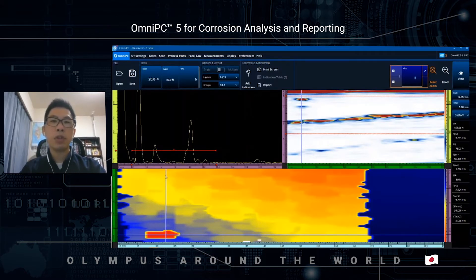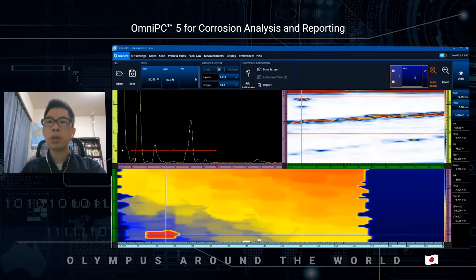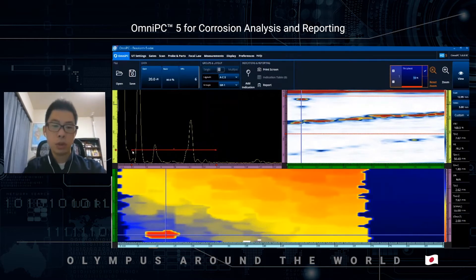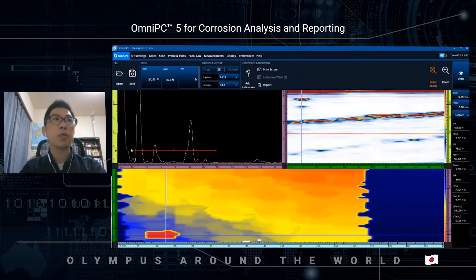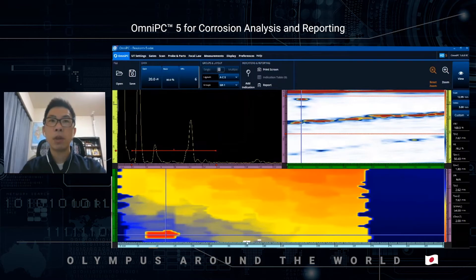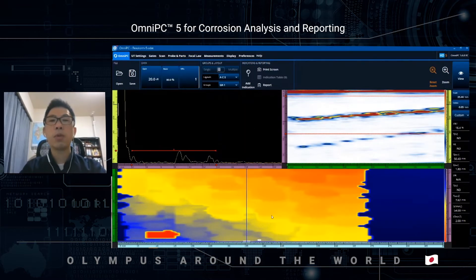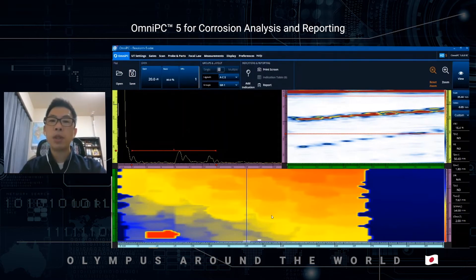Visualize the A-scan and ensure that the reading is valid and not the result of the interface at 0 mm, like this. So you can edit the gate position like this. In this particular data, I think I don't need to change the start position of the gate. A data point where no indication is detected in the selected gate will result in a white pixel, like here, and will not corrupt the readings. It is normal to have some missed data points due to unfavorable beam orientation from the corrosion.